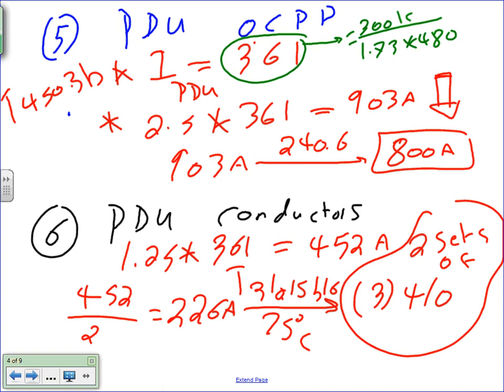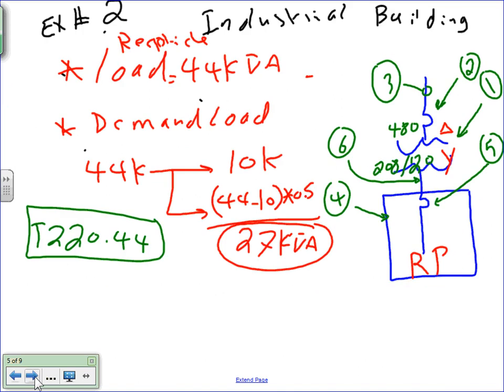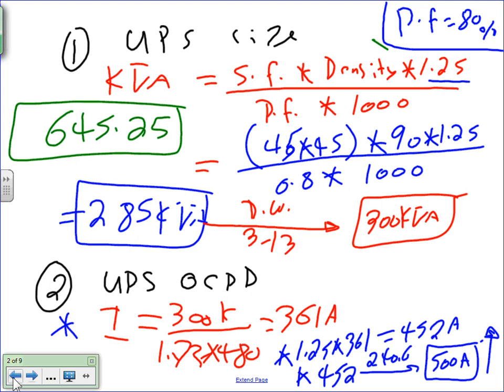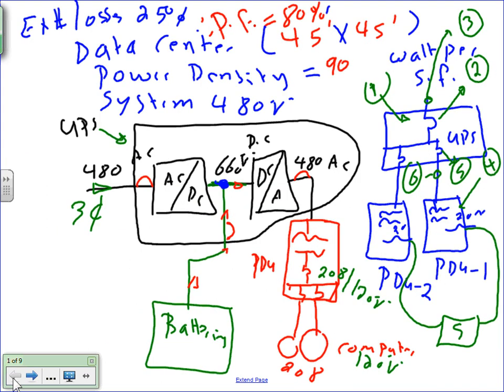Now the question would be, what happened to the secondary side? Let's go back here. Can you guys see the secondary side here? Is there a secondary side? The transformer is completely bussed into the panel. They're bussed to each other. So I don't have any secondary here. They're bussed together, meaning it's sized by the manufacturer. So what I was sizing is just the overcurrent protection device and the feeder, these two, typically.